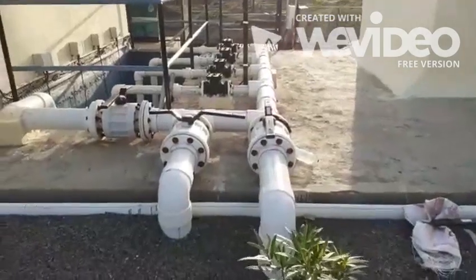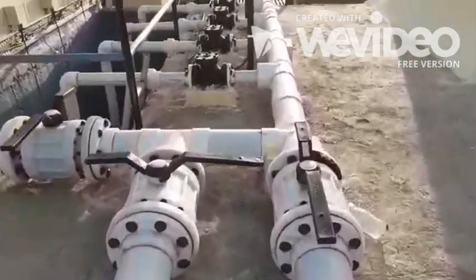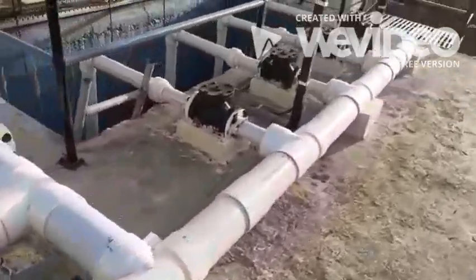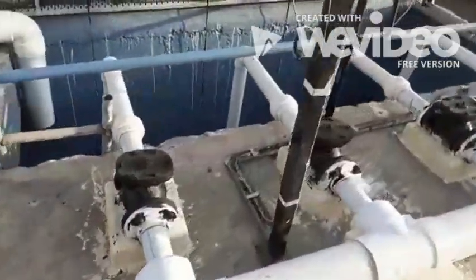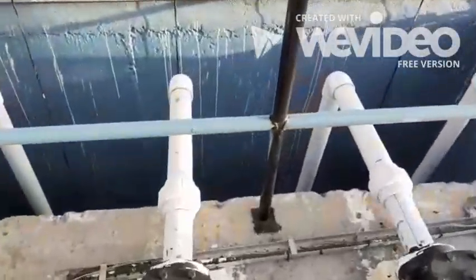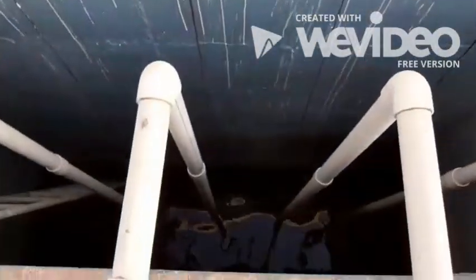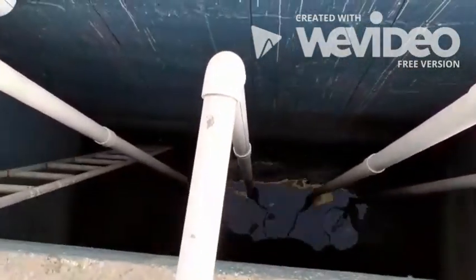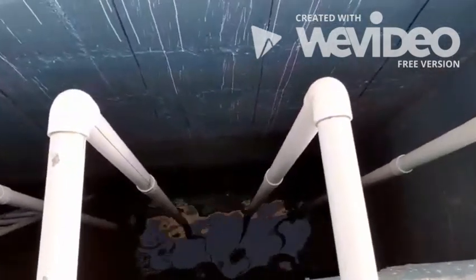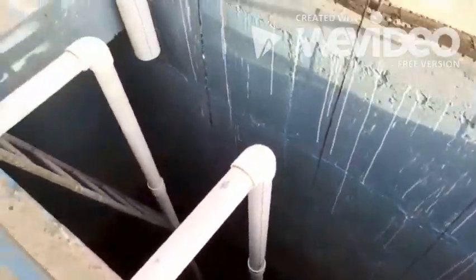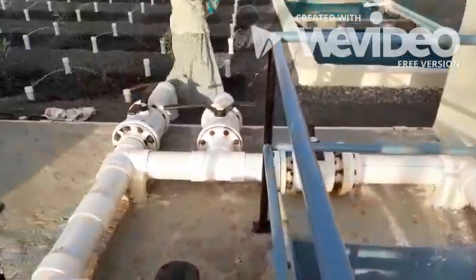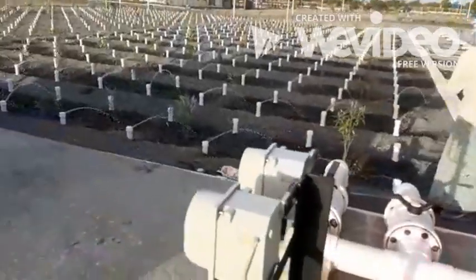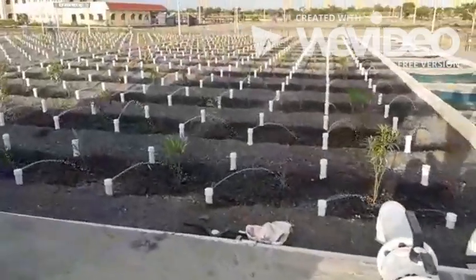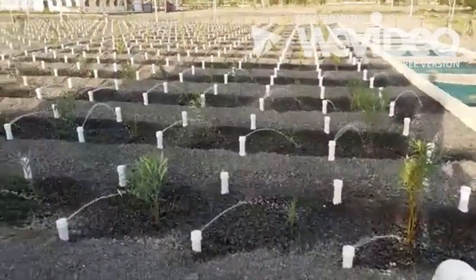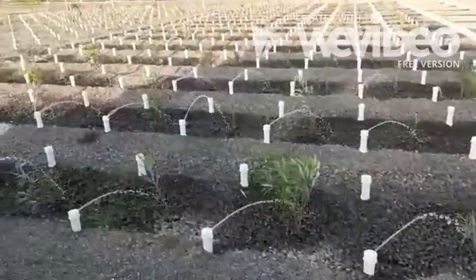The equalization tank is provided with multiple pumps, and it transfers the clarified sewage from the equalization tank to the next stage. The equalization tank is designed to handle the peak flows of the system. The pipes here are connected to the header of biomound 1, where the nitrification process takes place.